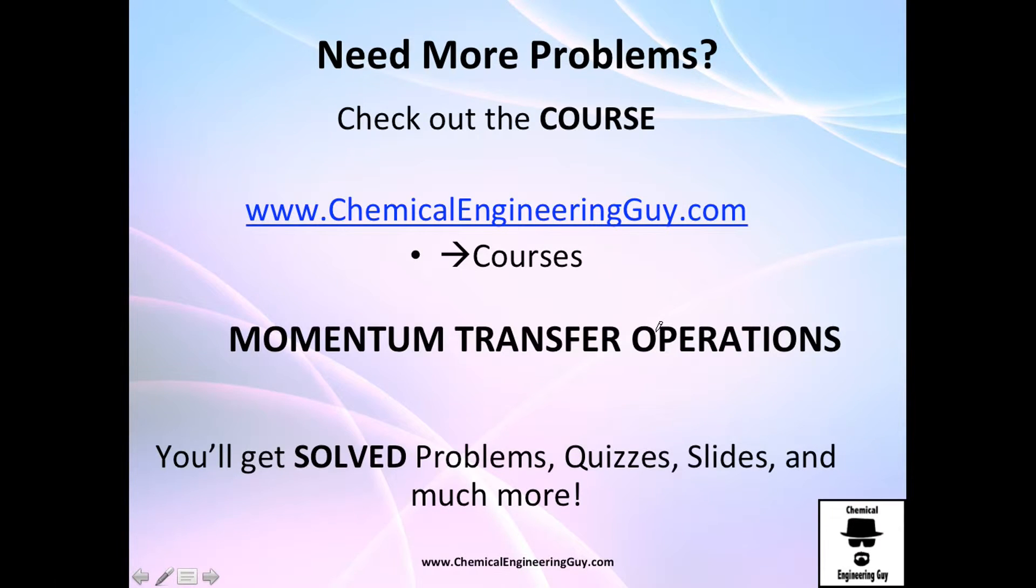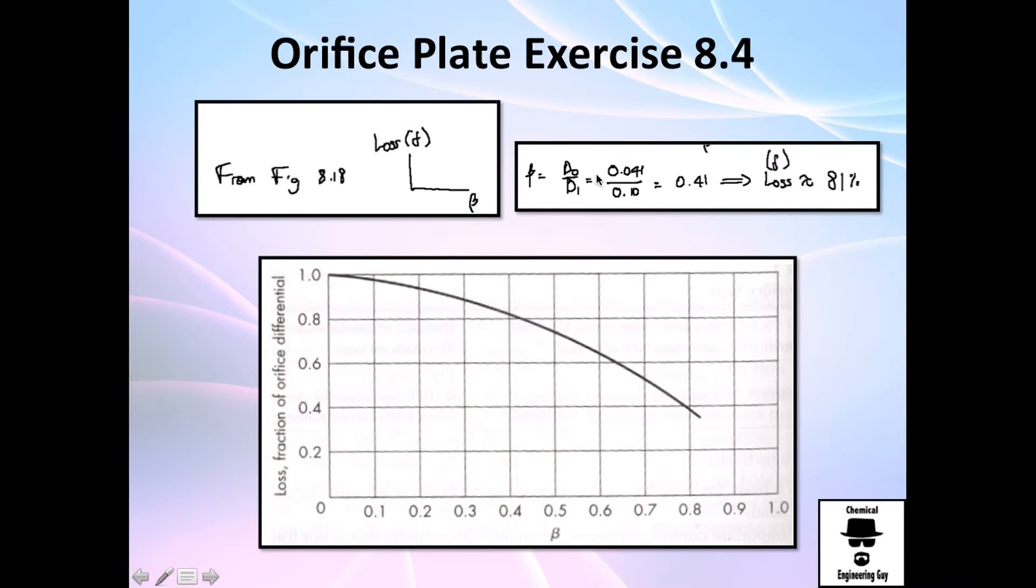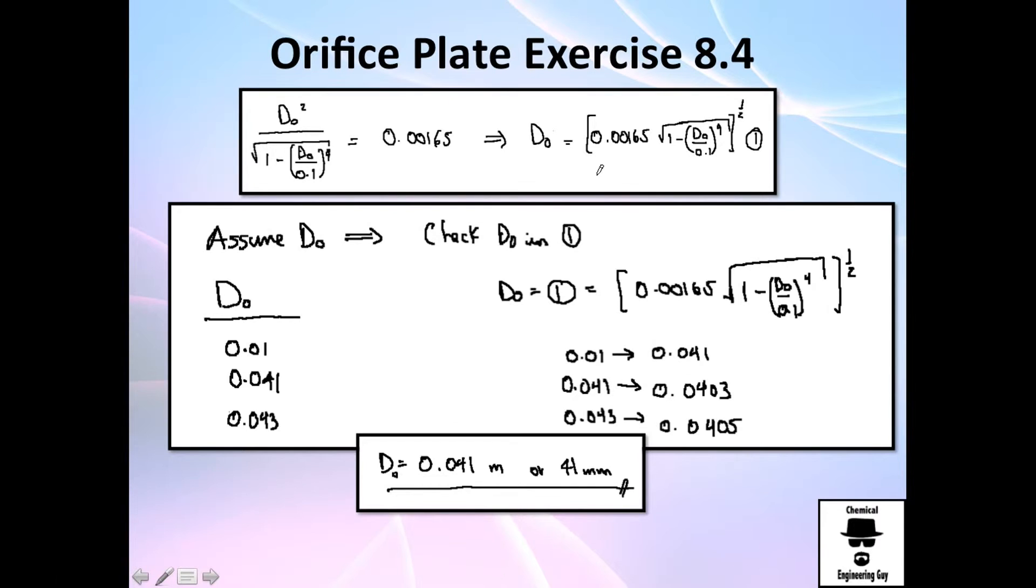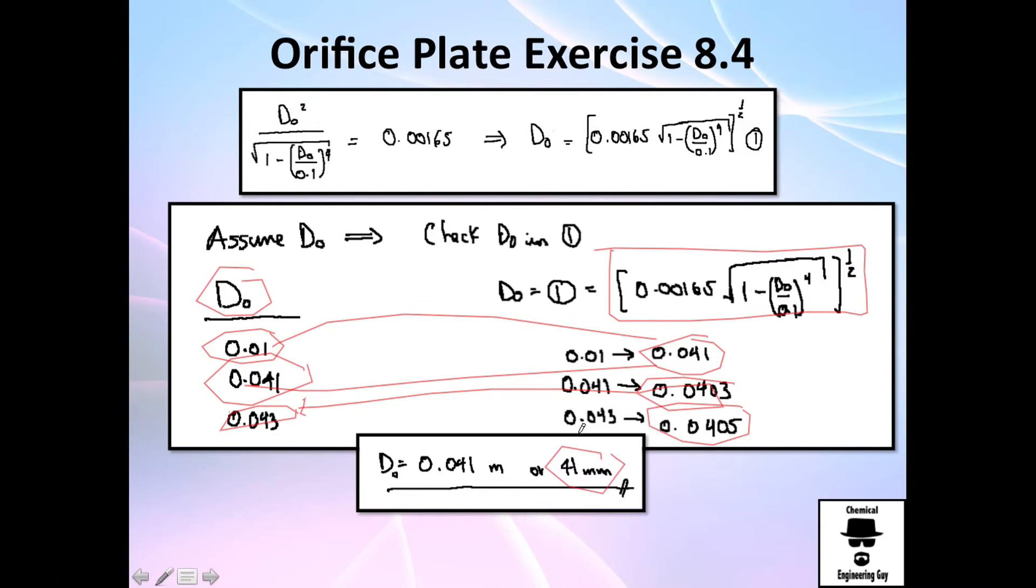So this one, if you checked out the venturi tube before, this one is a little bit more tricky because we don't have diameter of the orifice. And because everything is based on the diameter of the orifice or the throat, we got problems. We had to make this equation right here and propose many diameters and wait until we converge into a value. In this case, it was pretty easy. 0.01 goes directly to 0.041, I tried 0.041 again and I see that it won't change, so that's why I choose 0.041 m and 41mm.